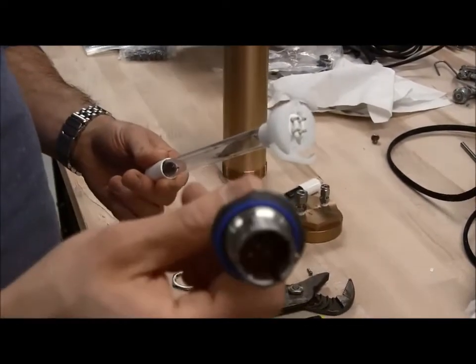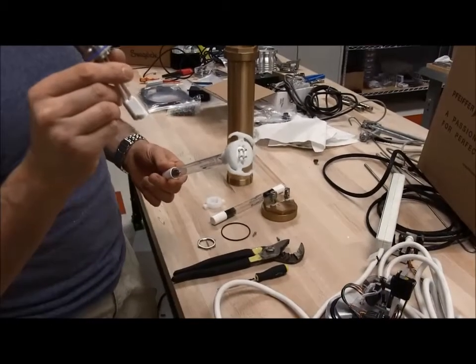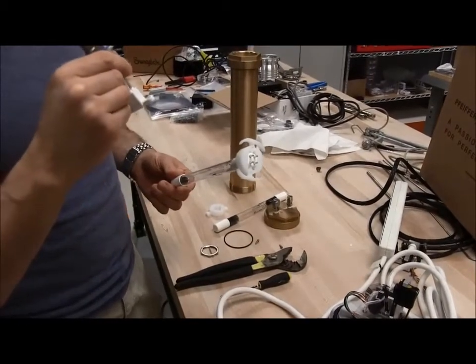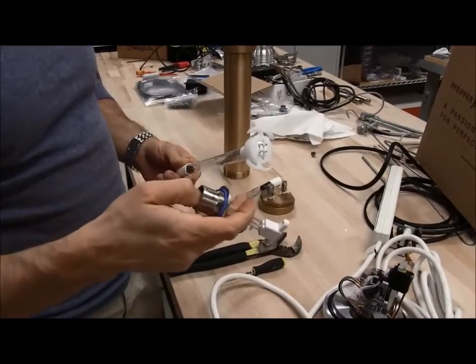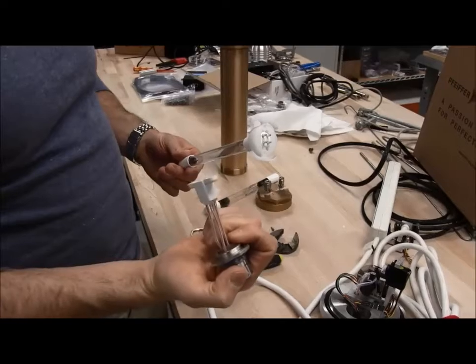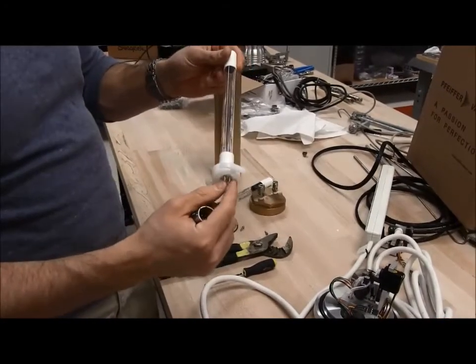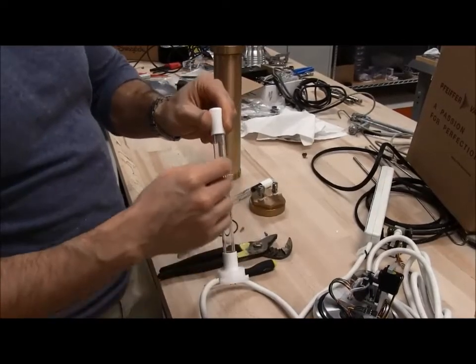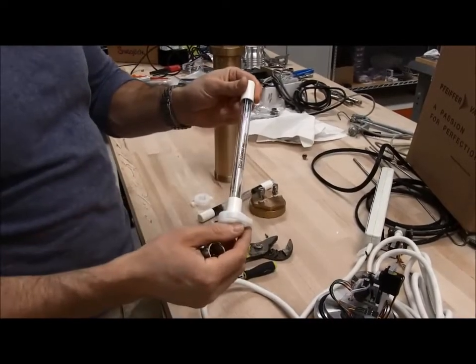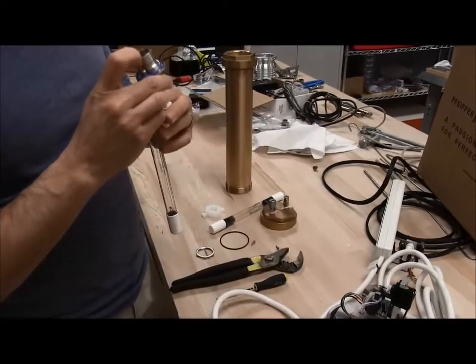Inside the connector, there are four pins that are bigger than the others, pins C, M, L, and G. Pins C and M should have wires that extend so that they are connected to the two pins that extend to these wires that traverse the length of the lamp to the far filament. So you'll just want to make note that those two pins end up like that.